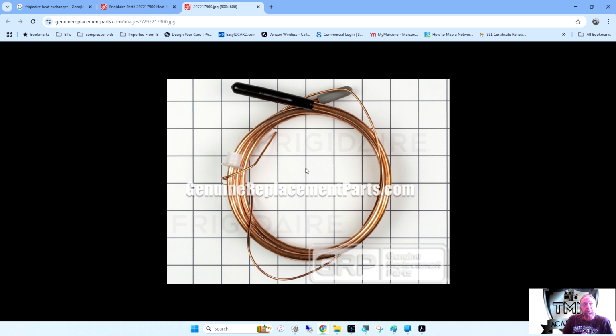What you're going to do is not remove any length of capillary tube, but you can remove suction line. Usually I take a torch with very low heat, heat up the pipe, and pull the capillary tube away from the suction line - they use more of a plumbing solder to join the two. I heat it up, pull the capillary tube away, cut off the excess suction line, then take the capillary tube and wrap it around a flux bottle, a can, or a flashlight, and use zip ties to keep that excess capillary tube back there. Other than that, all the procedures I do in that Frigidaire video are the same in every refrigerator.